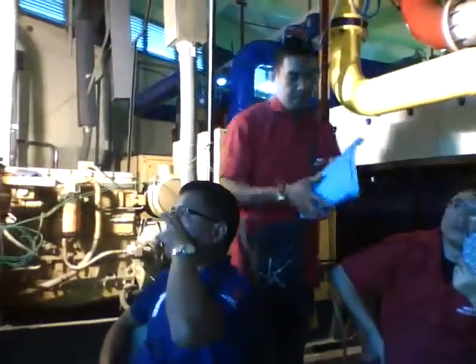Okay, so inside your maintenance manual, inside your OEM manual, there's a spot that actually says what all your maintenance guidelines are. I can't find it right now, but if you read through it, it tells you all the things that need to be checked. Quarterly, annually, yearly. It's mainly related to chillers. So tube punching, tower cleaning, pumps.